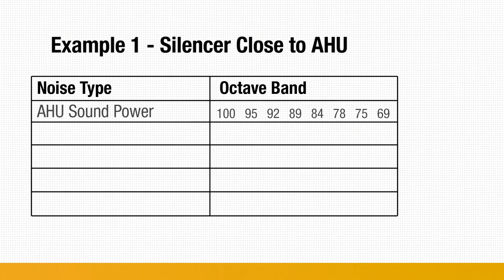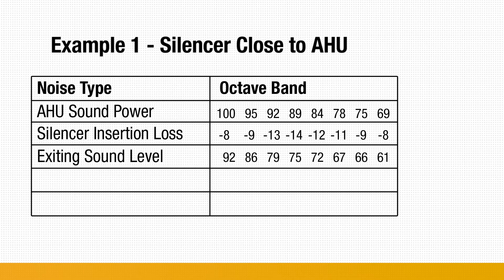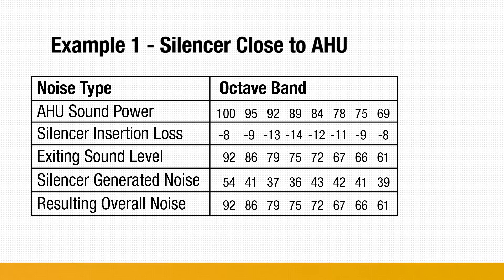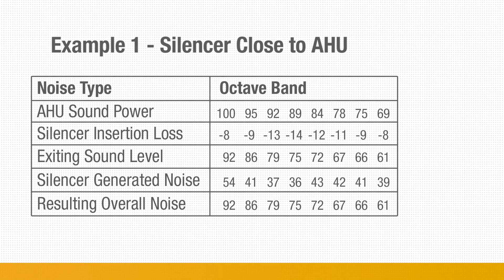In the first example, a silencer is located close to an air handling unit. The air handling unit's sound power levels are reduced across each octave band based on silencer insertion loss performance. The resulting noise levels represent the exiting sound levels of the silencer. When the silencer's generated noise levels are logarithmically added to these exiting noise levels, there is no contribution to the overall sound levels because there is more than a 10 dB difference between the generated noise and the exiting noise levels. As a result of this 10 dB difference, the silencer's generated noise is not a concern.